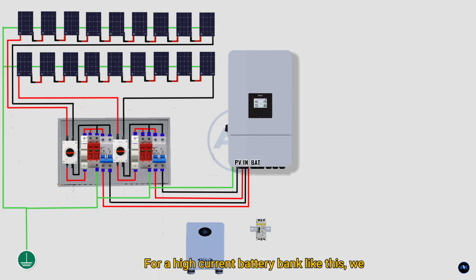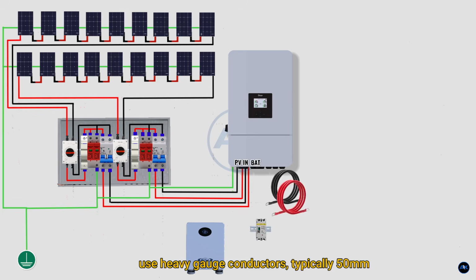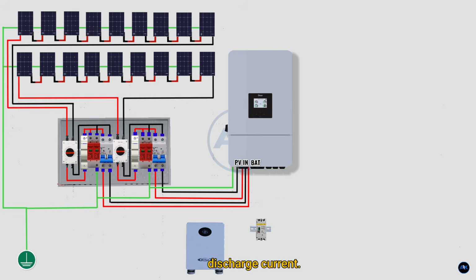For a high-current battery bank like this, we use heavy-gauge conductors, typically 50mm copper cables, to safely carry the battery discharge current. Double-check that the cable lugs are crimped tightly and that the heat shrink insulation is properly applied to prevent accidental contact. Now we can connect the battery to the hybrid inverter.